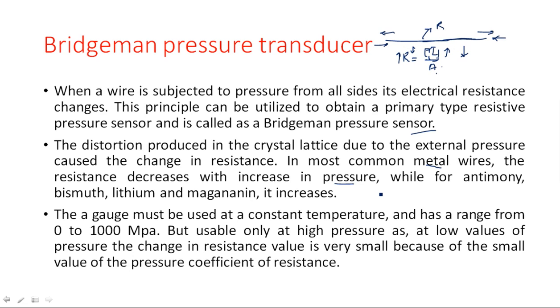The gauge must be used at a constant temperature and has a range from 0 to 1000 MPa. However, it is usable only at high pressure, because at low values of pressure the change in resistance is very small due to the small value of the pressure coefficient of resistance. The remaining pressure measurement types will be discussed in the next video.